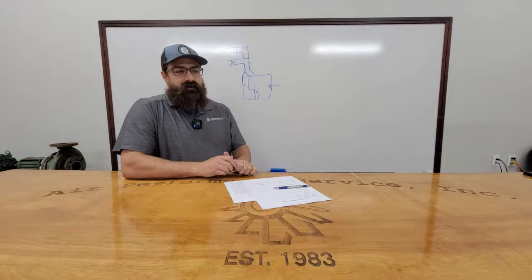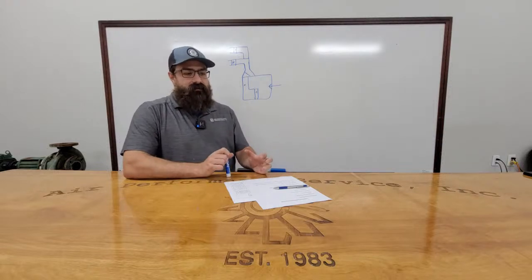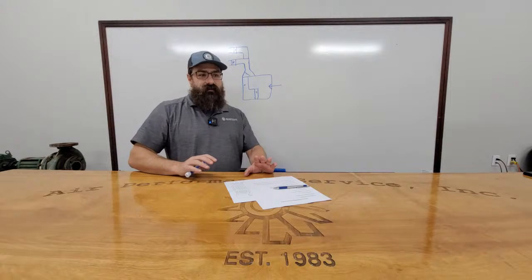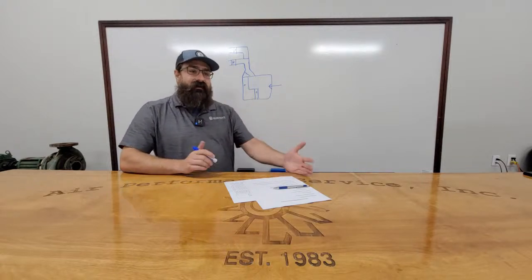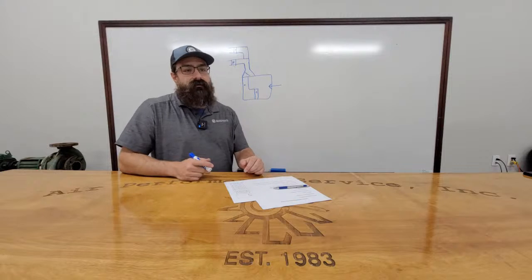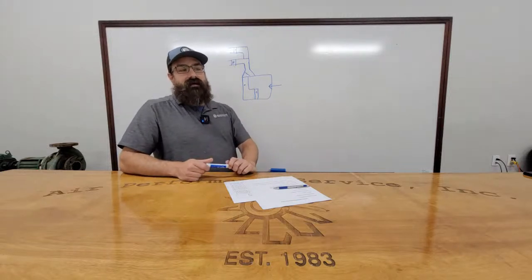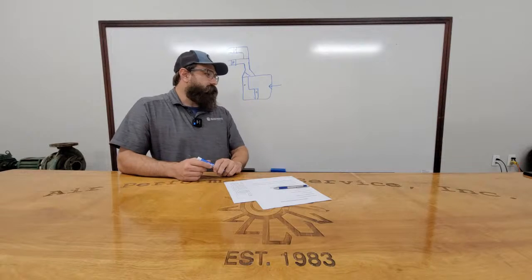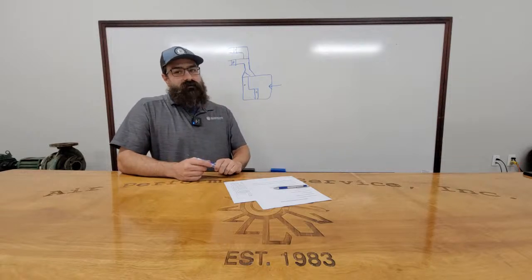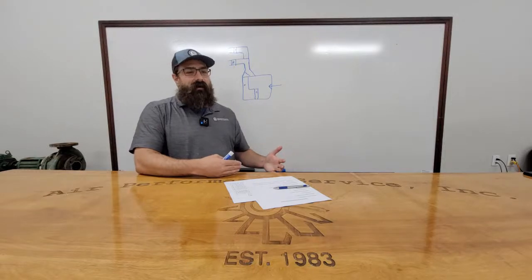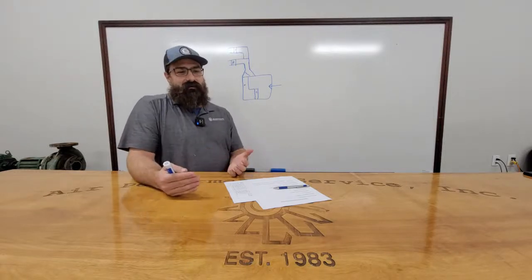Neutral. Yeah. So you can either have passive or active outside air. Passive would be it's just drawing it in, no cooling, no heating, no nothing. Then you can have active outside air, which would be heated and cooled to temper to space. Typically most outside air is going to be controlled to a neutral set point, because you don't want to bring in 45 degree air when you're trying to heat everything up, and you don't want to bring in 100 degree air when you're trying to cool everything down.